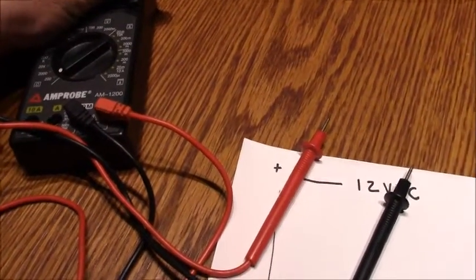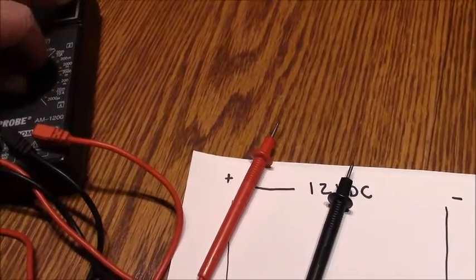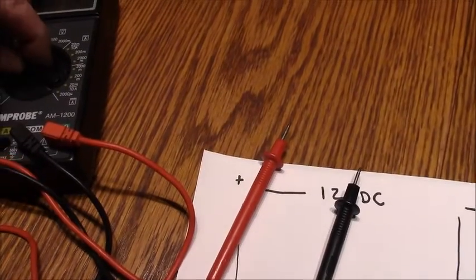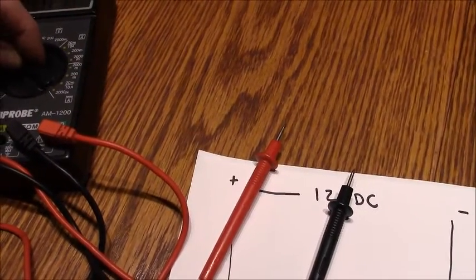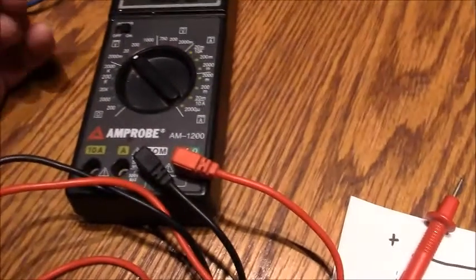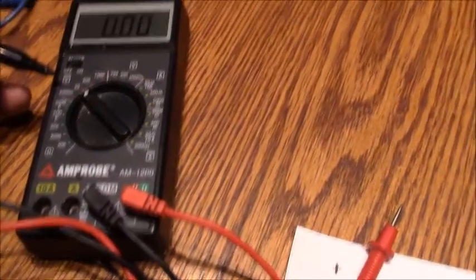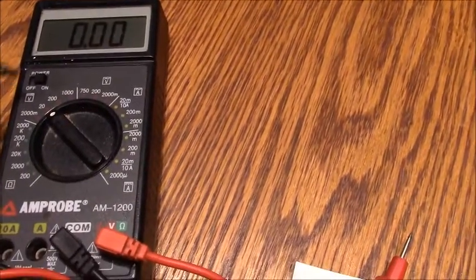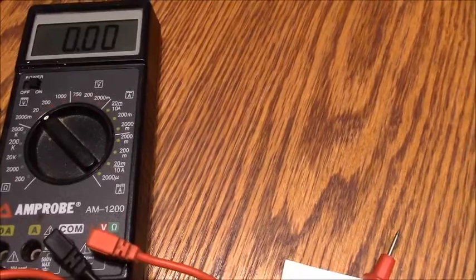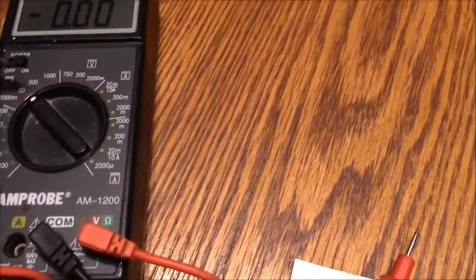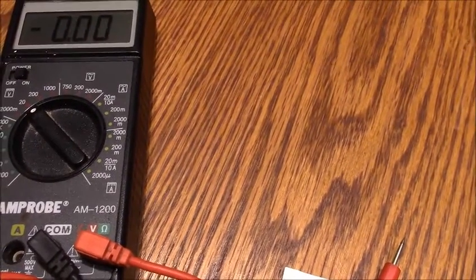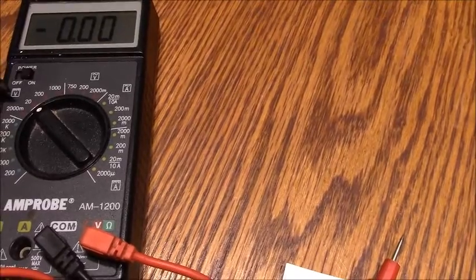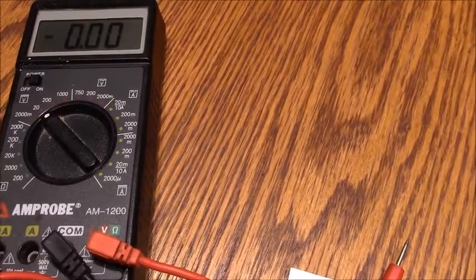To do that, you'd first ensure the electric meter is set to read DC voltage—in this case by moving it to the 12 volt DC indicator. It doesn't say a specific 12 volt range, but gives up to 20 volts, so you set it for the up to 20 volts DC range and take a reading.